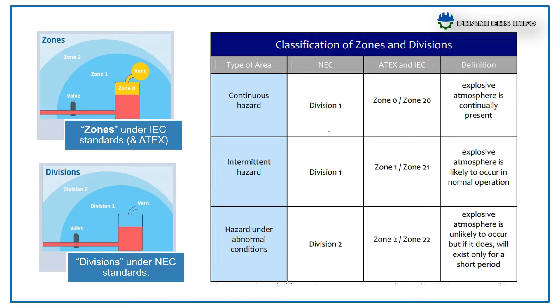Next one, flammable material classification. Depending on their properties, gases and dusts are classified by groups. These properties include factors such as ignition energy, auto-ignition temperature, upper and lower explosive limits, flash points, etc. Gases and vapors are categorized into three groups. They are 2A, 2B, and 2C. 2A for chemicals like acetone, methane, propane. 2B for ethylene, hydrogen sulfide, and 2C for hydrogen, acetylene, carbon disulfide.